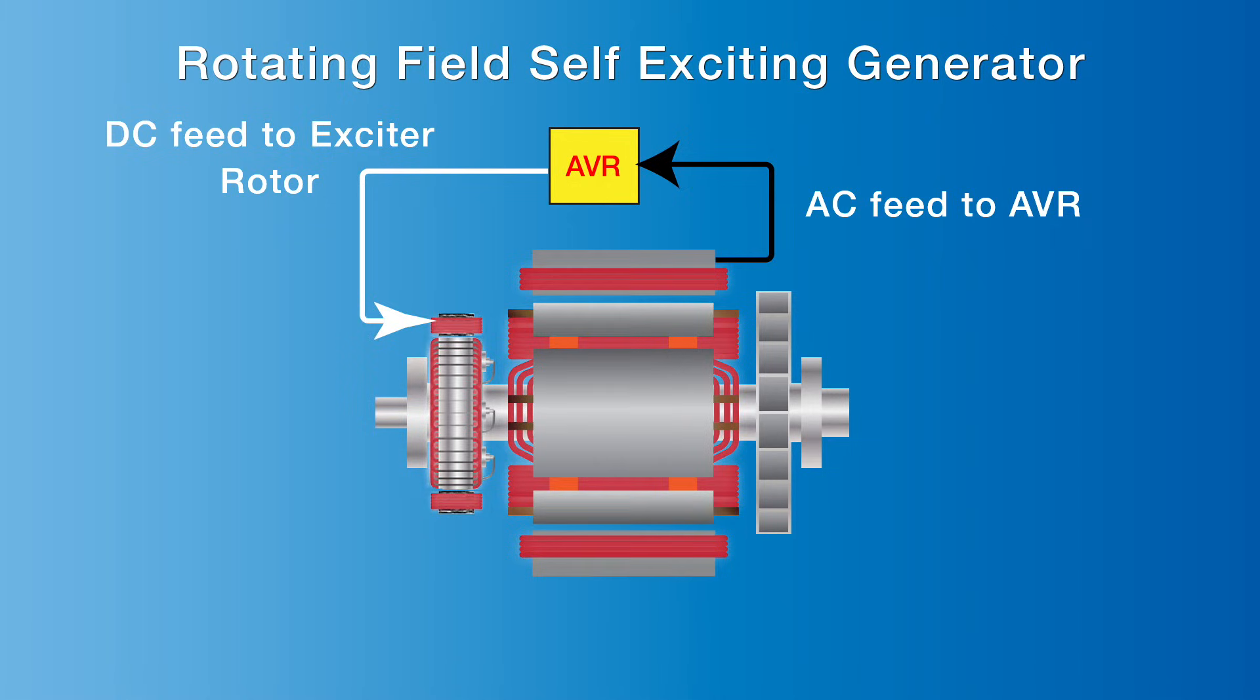A rotating diode assembly on the exciter converts this AC current to DC. The DC current fed into the main rotor windings also generates a magnetic field.